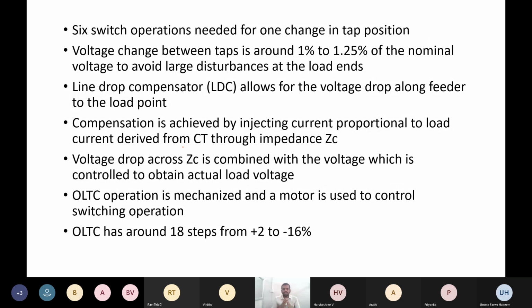So this voltage difference between the taps should be around 1 to 1.25% of the nominal voltage. So if you are applying 220 volts, just as an example. Normally at the tap position, the transformers will be of high voltage ranges. I am considering this for example purposes, take it as an ideal condition.